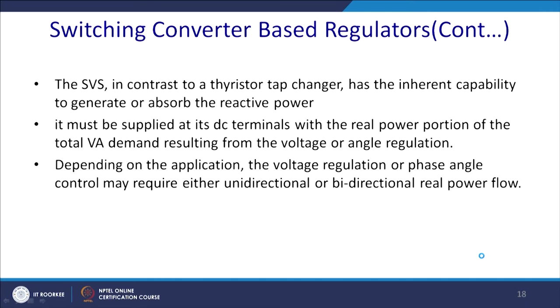Now, switching of the converter based on the SVC: what is the difference from the discrete component based thyristor? The SVC, in contrast to the thyristor tap changer, has the inherent capability to generate or absorb reactive power. This is one of the biggest advantages of it. It must be supplied at its DC terminal with real power. That is one of the requirements, you require a power source. Real power is the portion of the VA demand resulting from the voltage or angle regulation. Depending on the application, voltage regulation or phase angle control may require either unidirectional or bidirectional flow of real power. So that is something we require to keep in mind while designing that SVC based PAR.